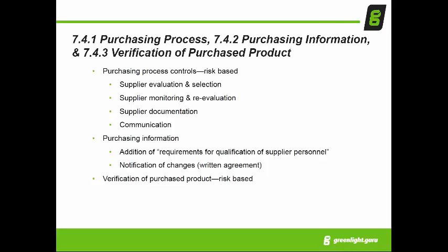When you're identifying suppliers and where you're going to buy and purchase materials, components, services, whatever the case may be, you need to be using risk-based decision-making processes on those suppliers. And the risk that component or that material or that service poses in your finished medical device is directly commensurate with the level of control and scrutiny and monitoring that you need to put in place for your suppliers.